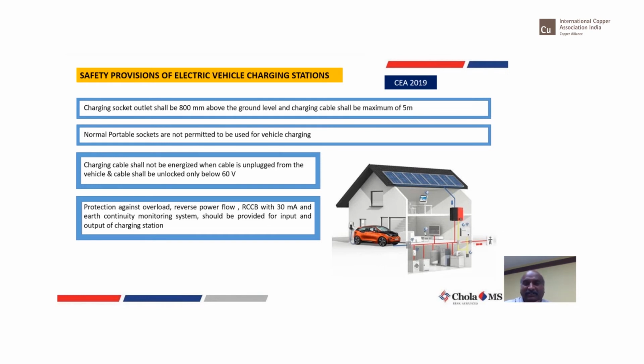Normal portable sockets, like in the garage, where I'll just put in the plug top? No, that's not allowed. They have clearly specified that the charging cable shall not be energized when the cable is unplugged. In a normal home, a typical example is our cell phone charger. Many a time you and I would have just removed the phone and gone. When we have removed the phone, the charger is still fixed in the socket, the switch is on, the charger circuit is on, and there is some voltage available at the end point. But in a charging station, they are saying clearly that even if you disconnect the cable from your car or two-wheeler, there should be a provision that the wall socket will disconnect the supply.